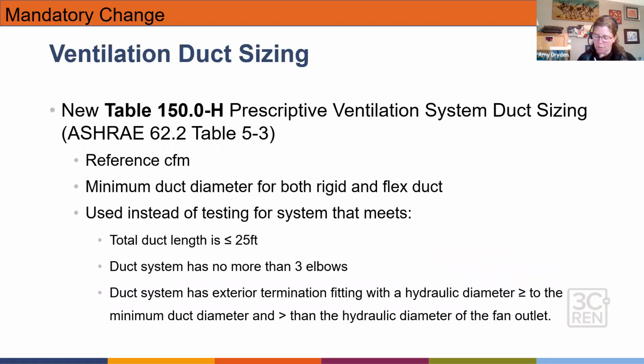Great. So for ventilation duct sizing, we have prescriptive standards now. They're referencing the CFM. They have a minimum duct diameter for rigid and for flex. And so if you have a system that meets those bullet points below, in terms of the total duct length being less than 25 feet, not having more than 3 elbows, and the exterior termination not being smaller than the duct diameter, then you can utilize this table to have that reference CFM and that minimum diameter to meet requirements. There still is testing for ventilation performance with HERS testing to document the CFM delivery.